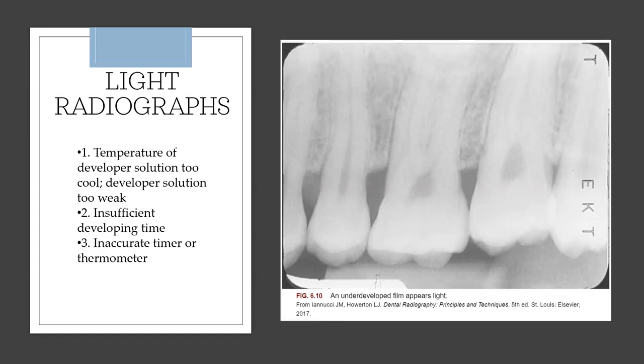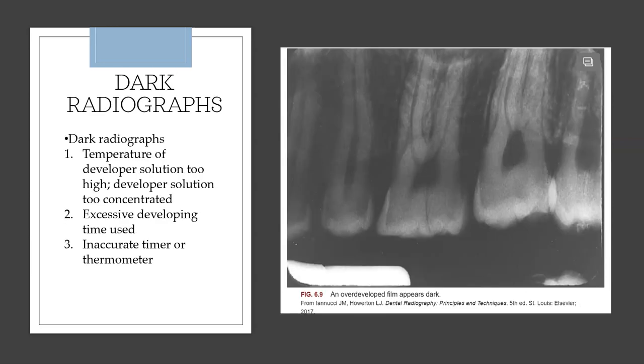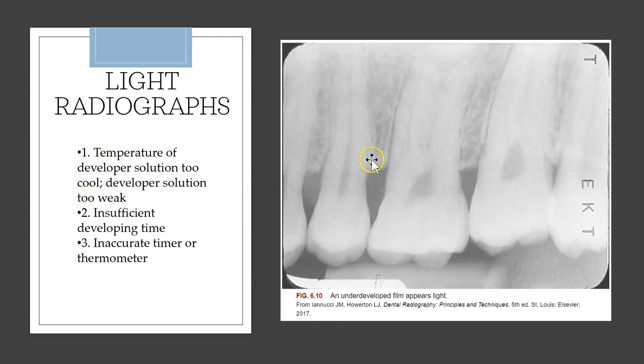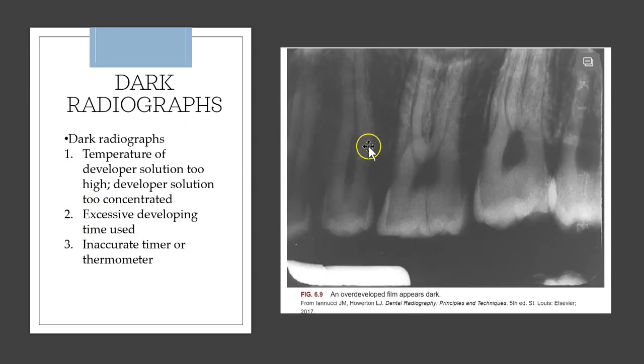A light radiograph is an underdeveloped film, which can happen when the developer solution temperature is too low (too cool). Memory aid: low temperature = light image (both L's). High temperature = dark image.